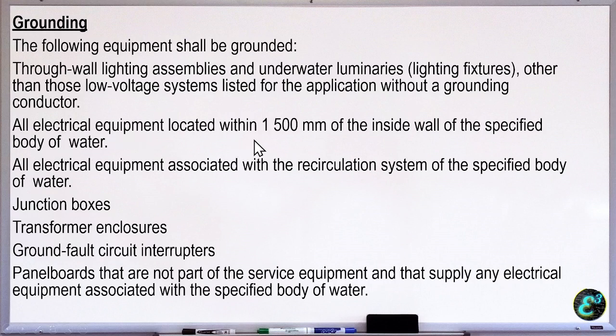Any electrical equipment located within 1,500 mm of the inside wall of the body of water. So from the wall of our swimming pool, 1,500 mm from there, as long as there is equipment, motor, lights, receptacle, it should be grounded. All electrical equipment associated with the recirculation of water system of the specified body of water. So for example, the pump motor that suctions water from our pool will be grounded.